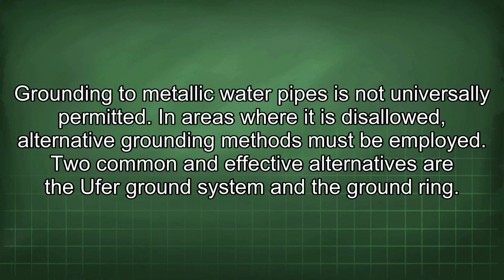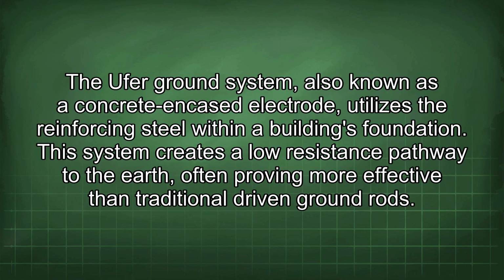Grounding to metallic water pipes is not universally permitted. In areas where it is disallowed, alternative grounding methods must be employed. Two common and effective alternatives are the Ufer ground system and the ground ring. The Ufer ground system, also known as a concrete encased electrode, utilizes the reinforcing steel within a building's foundation.